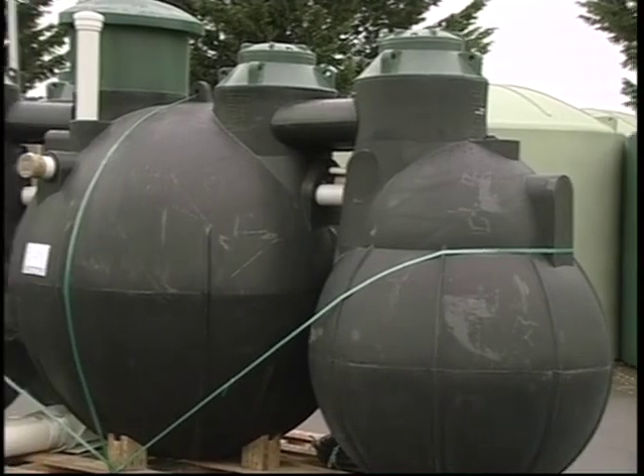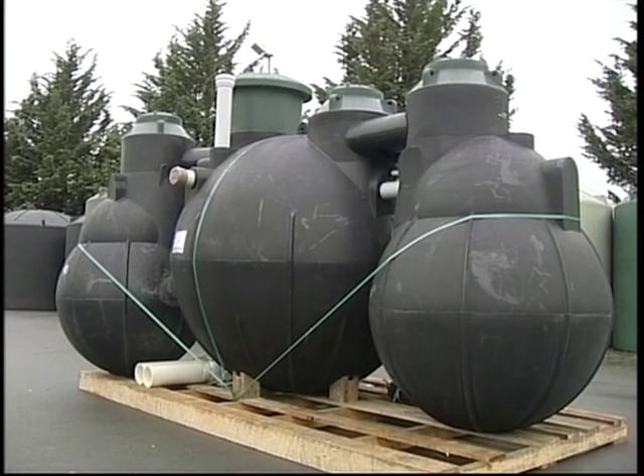So what about quality control? I know that RX Plastics with their MAX tanks have gotten independent people to keep quality up. Yep, that's correct. We also do that with our aeration units, Airtek units, and our standard septic tank range. Within the North Island, there's an independent trial called the OCET trials, which is run by Water New Zealand, a branch under that called Swan SIG. They do independent testing of our Airtek systems through about an eight-month trial period. They put through town wastewater, take samples regularly, and then overdose it, and deliver us a report. And that's reassurance for us, for the homeowner, and for the councils that the system does work.